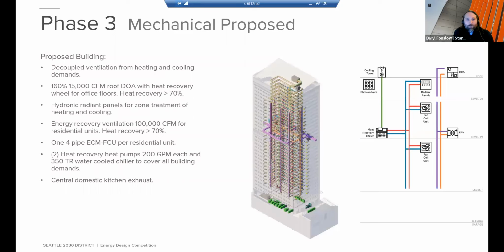It gets a bit more complex, but the main things we did were decoupled ventilation from the heating and cooling system. We added dedicated outside air units on the rooftop and at level 19. Rooftop units supplied air to the office on the upper floors, and the ERV on 19 provided ventilation for the residential floors. For heat recovery, we added a heat recovery chiller to meet the heating and cooling demands for the entire building, which really drove our EUI down — that was one of our key ECMs. We served office spaces with hydronic radiant panels, and residential units with 4-pipe fan coil units.